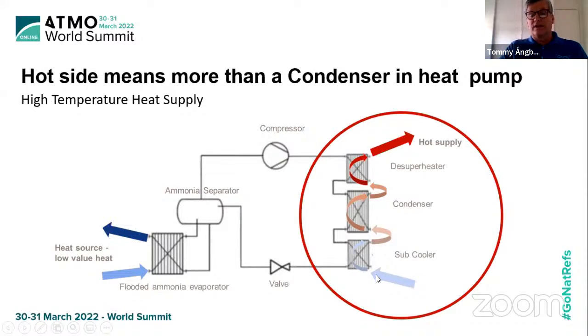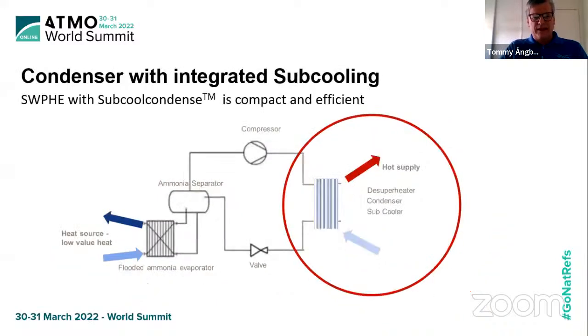Heating then the source that you want to heat through the three stations to the temperature required. This was typically done in the past, and in most cases, with three heat exchangers running in series: subcooler, condenser, and desuperheater. And that's fine. You can obtain good efficiency with this type of setup. But our latest development has been a plate heat exchanger with what we call the subcool condense. So we have a feature in the heat exchanger that is designed to do the three duties in one. This would secure the high performance. We'll come to how we can secure that later, but also we avoid a lot of piping and have only one heat exchanger.